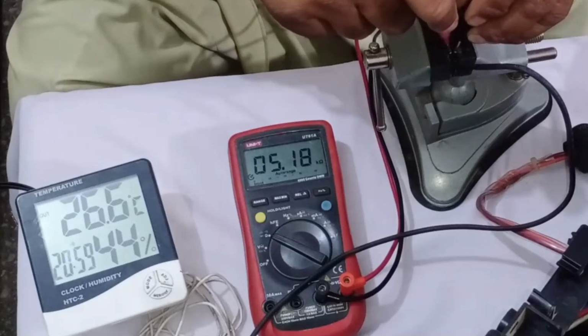Also, if the sensor is not properly installed in its correct position, the error will still appear. Any of these faults could be causing the issue, so you should check all these possibilities. Once you inspect and repair the faulty part, the error will disappear and the unit will return to working condition. The resistance value of this thermistor is 5.18 kiloohms.